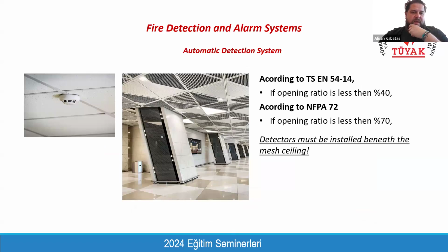And also, if you have this kind of grated ceiling, as we talked about for the sprinkler system, and you would like to locate your fire detectors within the ceiling void and you don't want to locate them beneath the ceiling, then the ceiling opening ratio should be not less than 70% as per NFPA, but it is 40% as per the European fire norm. If you'd like to omit fire detectors below ceilings, you need to take these opening ratios into account.